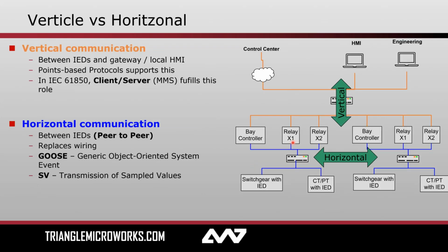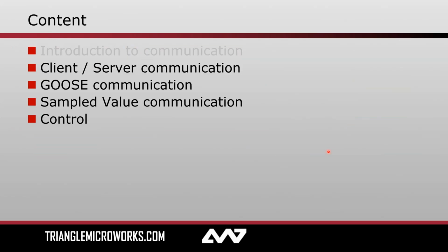Another way to think about this is vertical communication versus horizontal communication. If you see this diagram on the right-hand side, you'll notice that I have all of my IEDs down here at the bottom. These are servers and peers that are able to communicate with each other horizontally, whereas they're all capable of sending vertical communication up to my clients here at the top. Client-server communications, sometimes referred to as MMS, which I'll be speaking about more in my next few slides, falls under this paradigm of vertical communication. Whereas peer-to-peer, this is where GOOSE and sample values will exist, communications that are sent back and forth between the different servers. So we've gone through our introduction, and now we'll be taking a closer look at client server in particular.